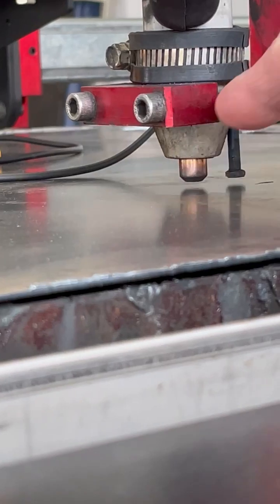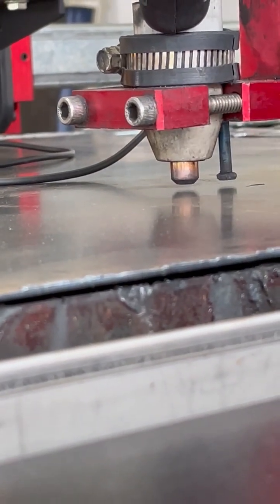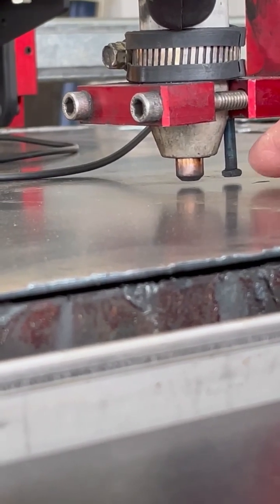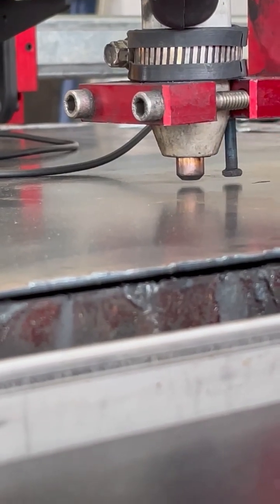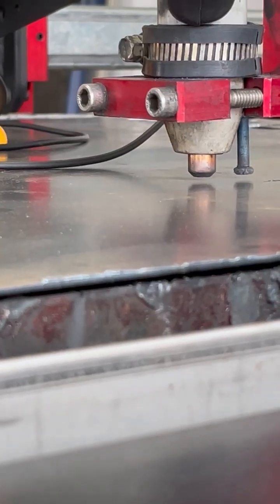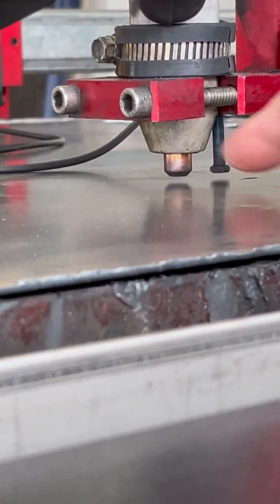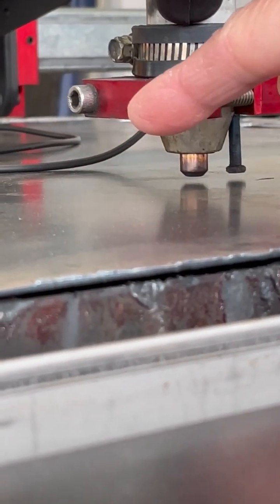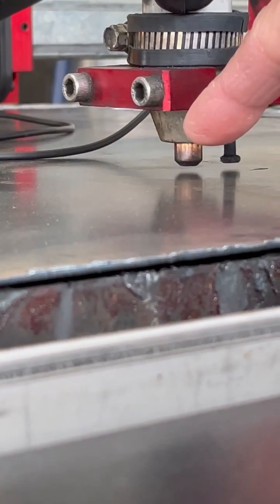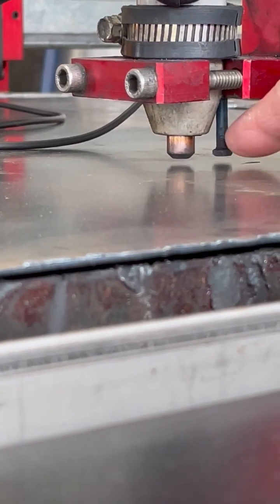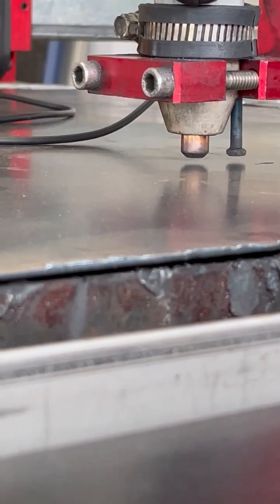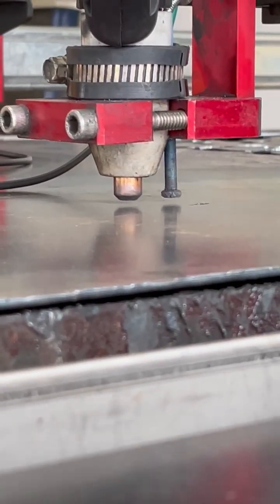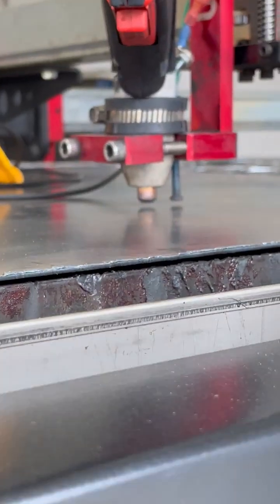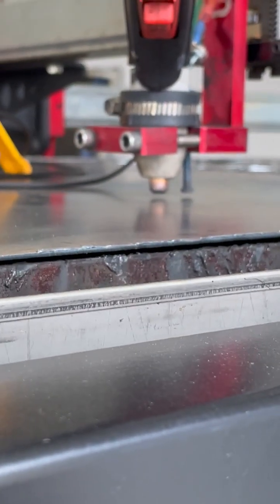Okay, so I had to do something, because if there is a bow at some point, if I adjust wherever this is traveling, if the bow is here and this is lower and this is lower, so this is higher, lower, lower, if the torch goes down anywhere over here, the probe will touch the material before the tip. So when it touches, there will be a gap, and that will throw off the cut height. The same thing is if this senses over here on the other side of the bow, then the tip will touch first, and then it will start to push the material down, and this will never touch the material. Okay, so my ohmic circuit will not be in play for that cut. So there's a solution for that, where I don't have to use that probe, and I can do my sense right from the tip there. Okay.